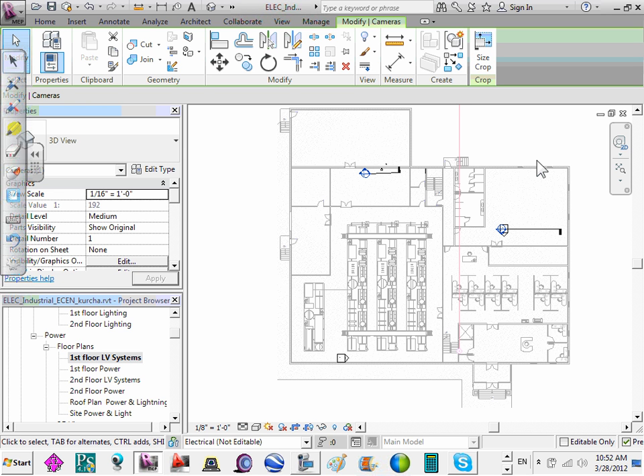But in open office areas, you can go 50 feet for notification. For strobes, depending on the candela and the height of the ceiling, you can reduce the amount of space, but we typically use 50 feet. Out in a manufacturing area like this, depending on the noise level, they're not really going to know that there's a fire alarm going on anyway. They'll hear something on the horns. If it's a speaker system, you can design it so they might be able to hear it, but intelligibility suffers with a lot of noise. That's why they have the strobes in there, because the strobe is going to be the main notification in noisy areas. Same as the speakers, 50 feet.